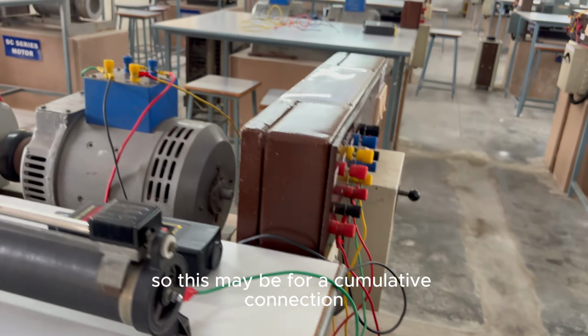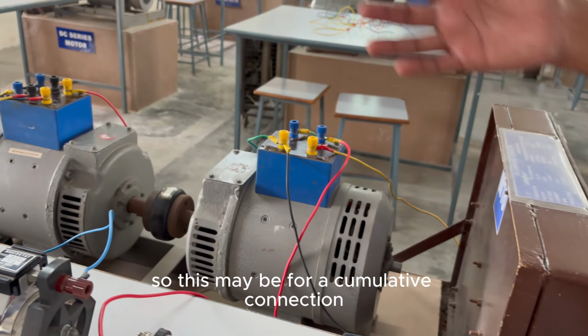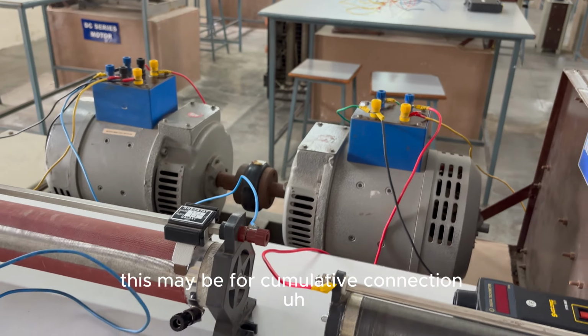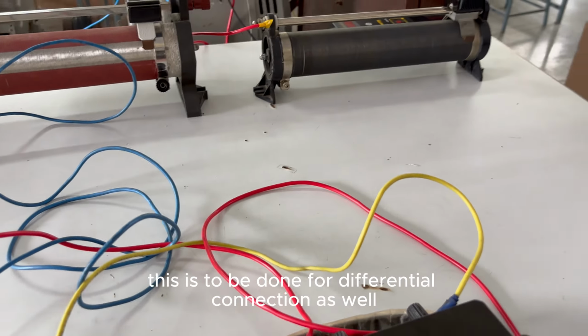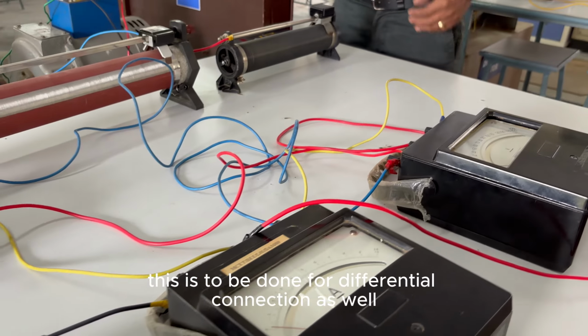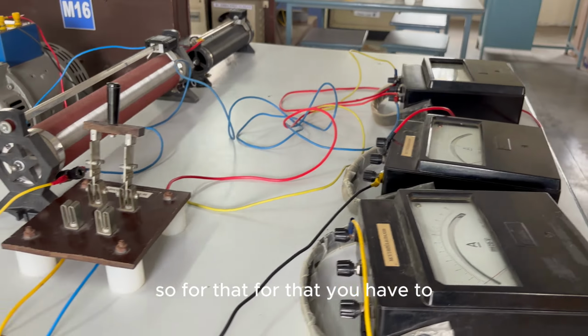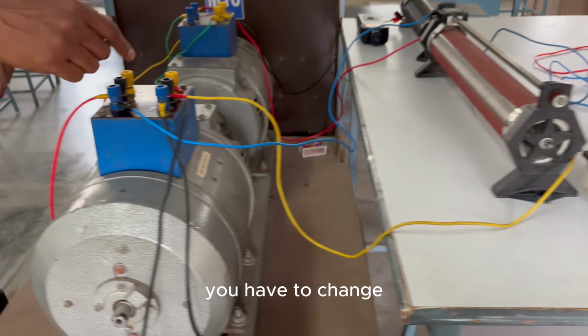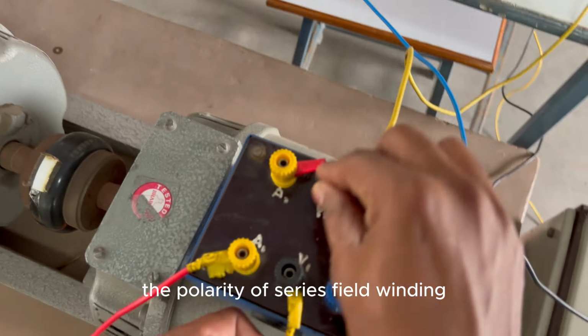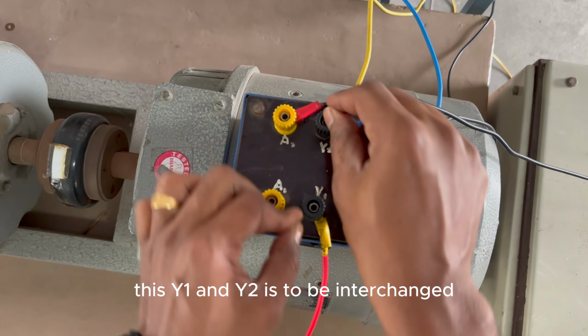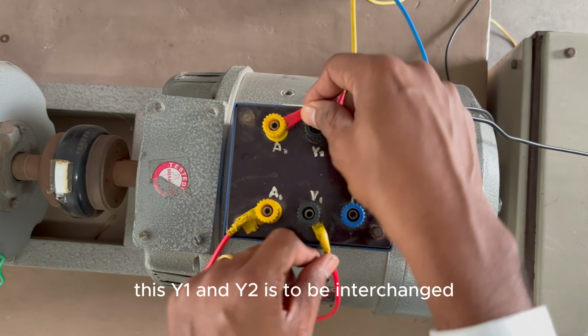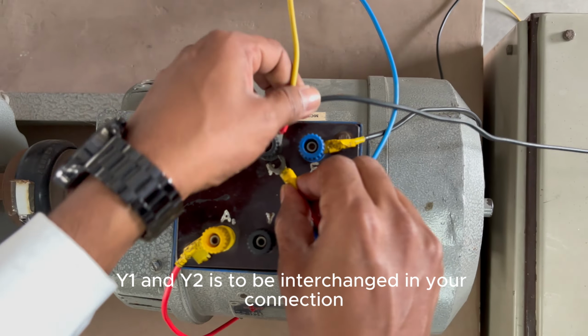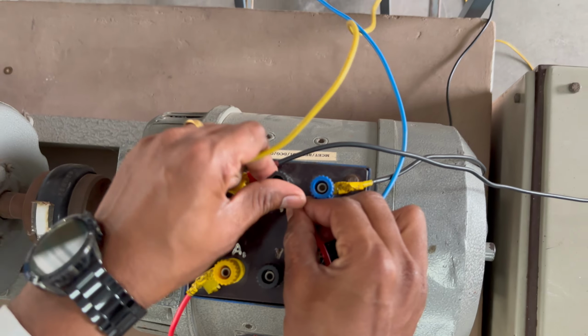This is for the cumulative connection in a compound generator. This is to be done for the differential connection as well. For that, you have to change the polarity of the series field winding. Y1 and Y2 are to be interchanged in your connection.